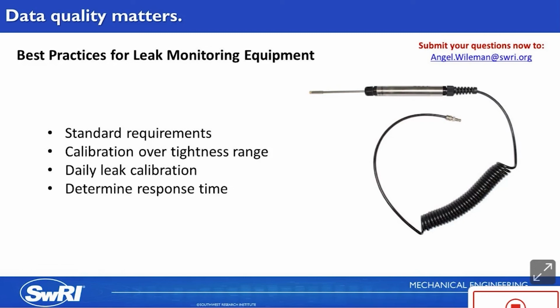Lastly, it's critical to determine the response time of the instrument to detect a leak, so the proper duration is used during testing, or else you may miss leaks. The response time is defined as the time between when the calibrated leak standard is opened and the moment when the reading of the instrument shows an increase in helium or methane.